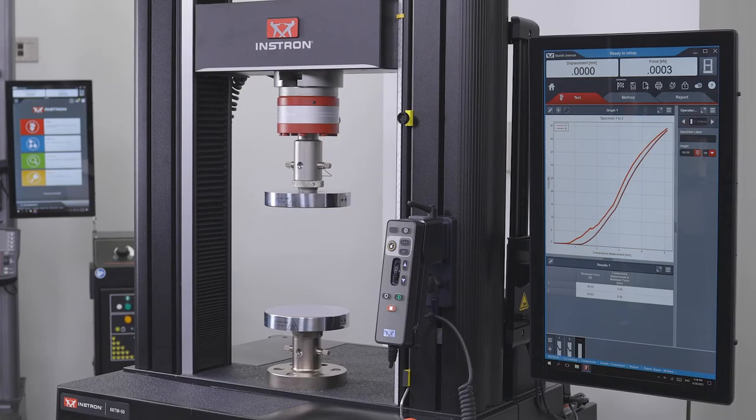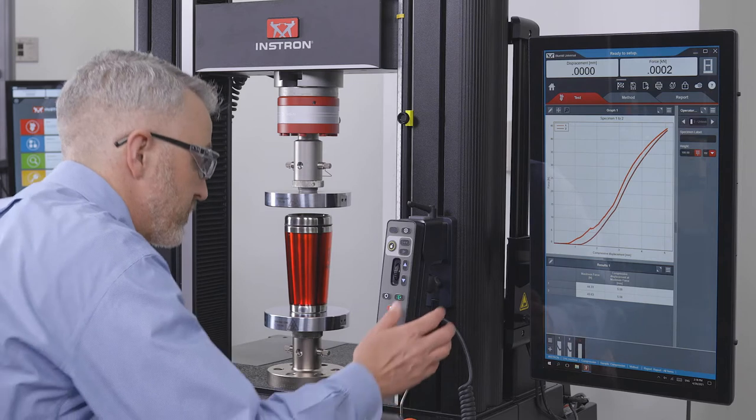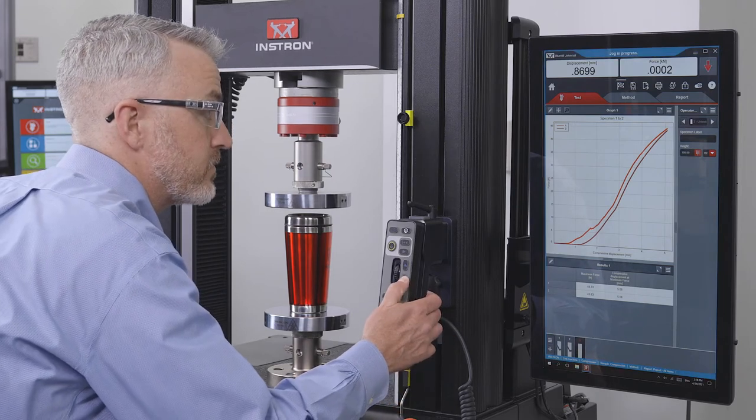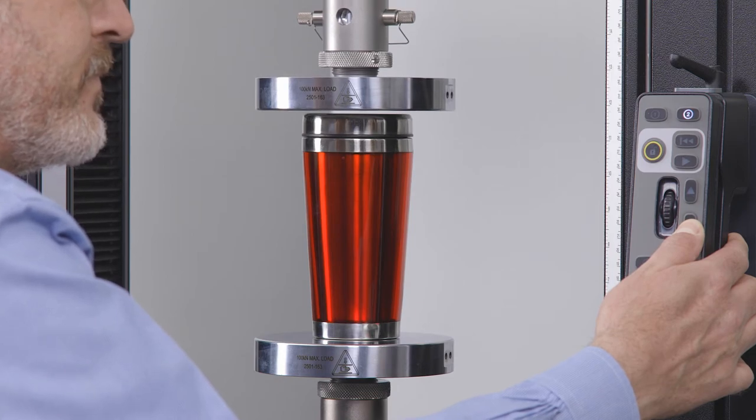Collision Mitigation is an enhanced feature that comes standard on all Instron 3400 and 6800 series testing systems. It is designed to stop crosshead motion anytime an unexpected force is detected during jogging or returning.